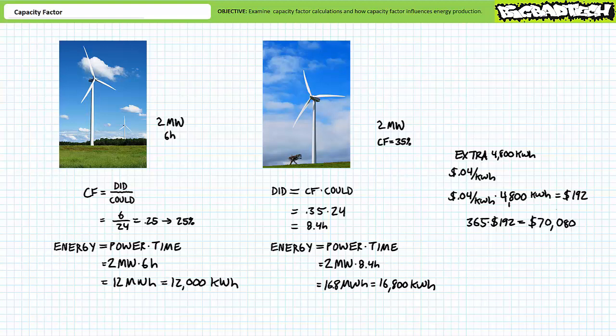If the owners were selling the output of this turbine at a wholesale price of let's say 4 cents per kilowatt hour, the turbine with the increased capacity factor would generate 4,800 times 4 cents or $192 more each day than the one with the smaller capacity factor. If this pattern repeated itself for 365 days or a whole year, this turbine with a higher capacity factor would have generated 365 times 192 or $70,080 additional dollars. As this example is intended to illustrate, capacity factor has a profound impact on the economics of energy production. It is for this reason that the wind resources of a proposed wind farm must be thoroughly investigated before development. Windier regions result in wind farms with higher capacity factor and more profitable results.